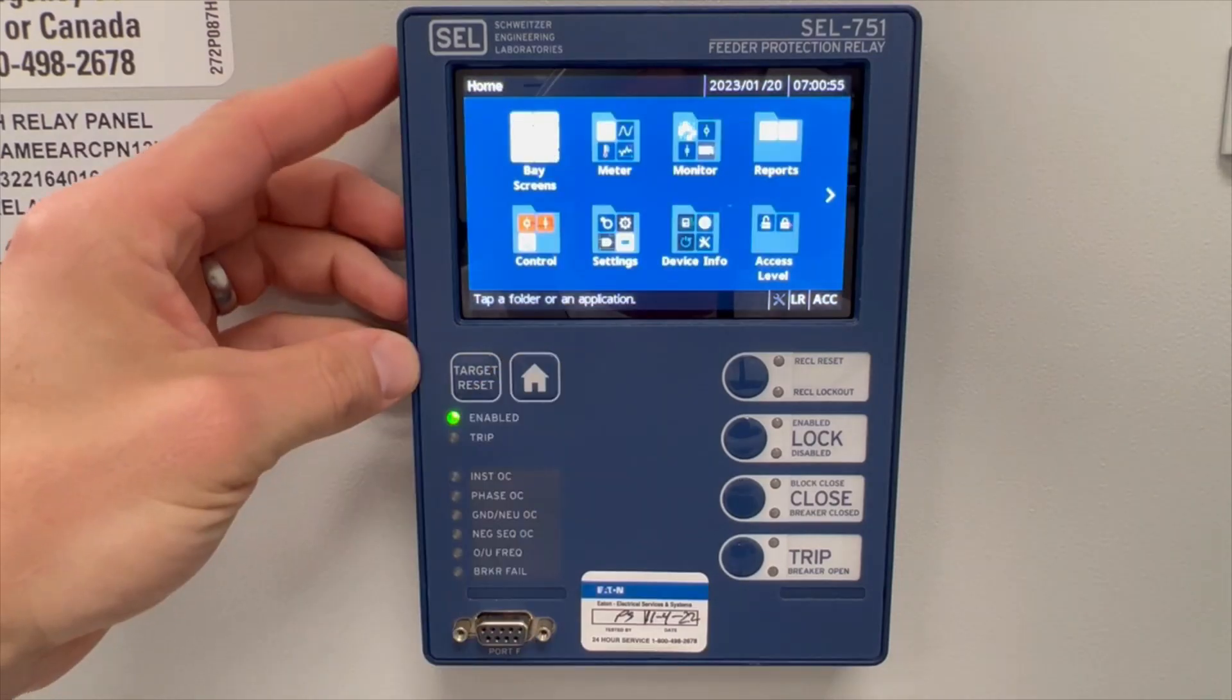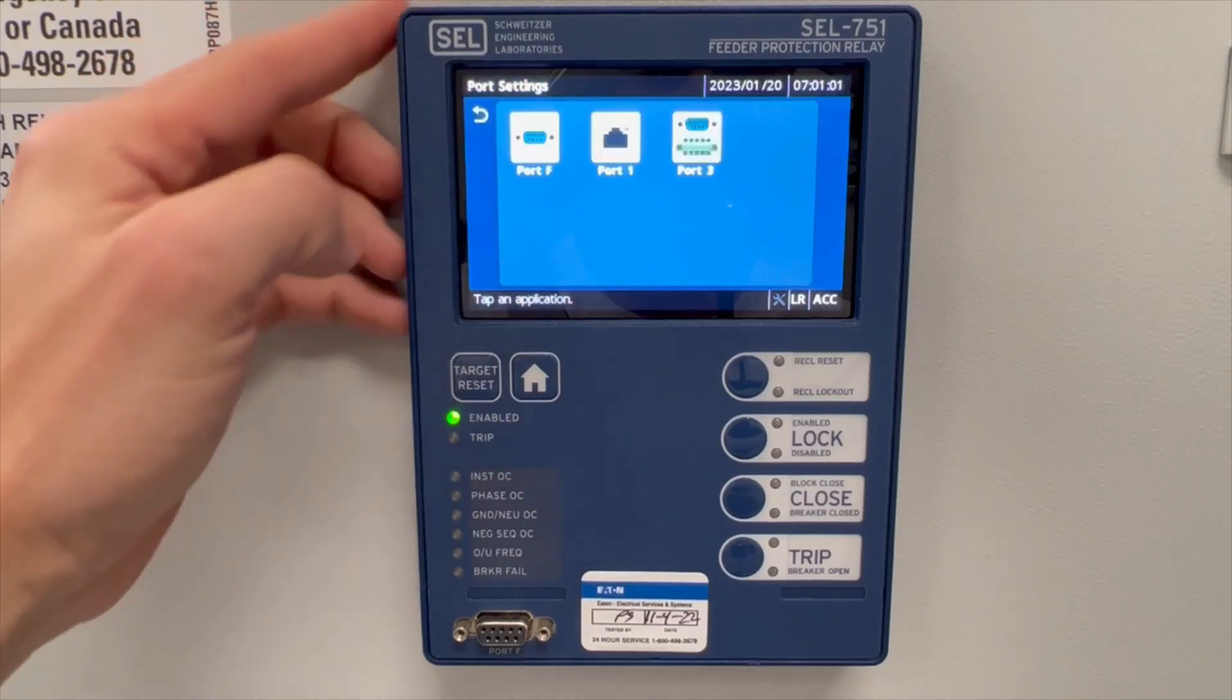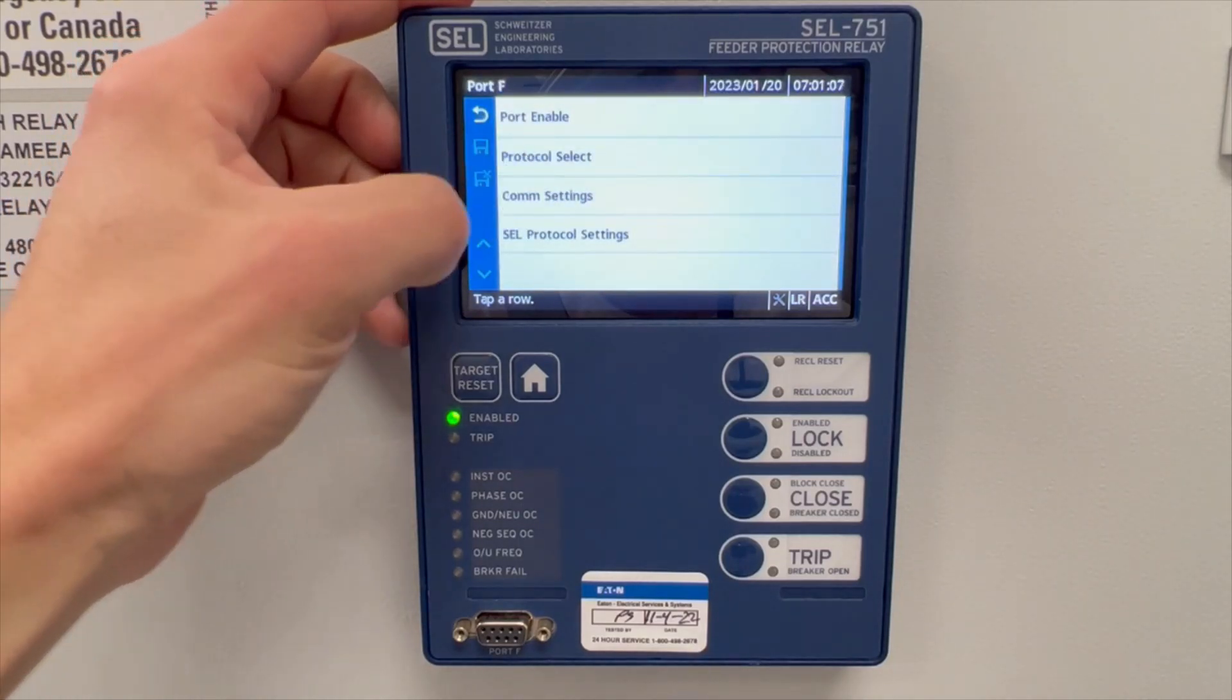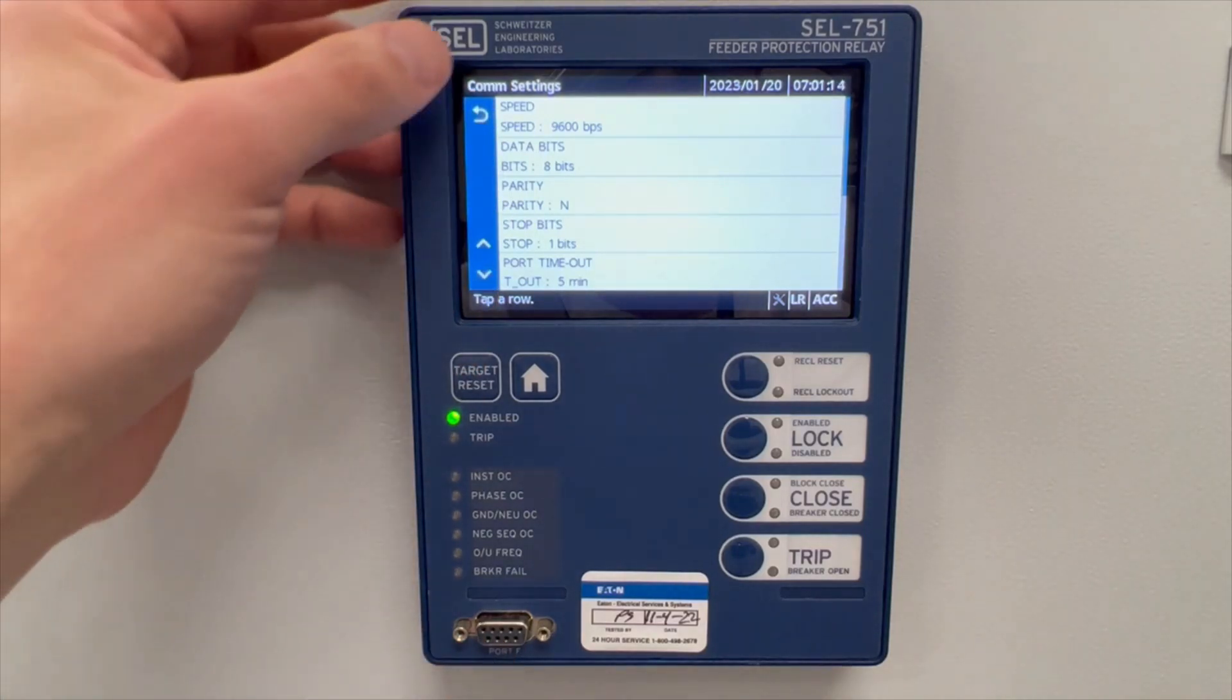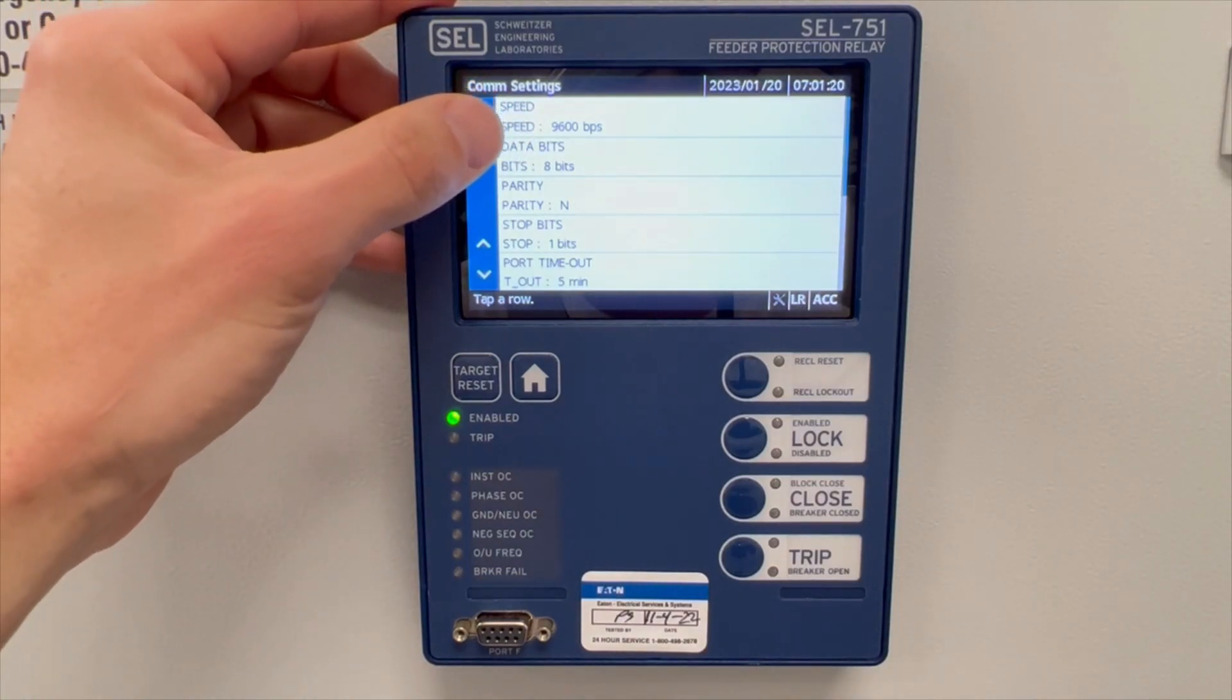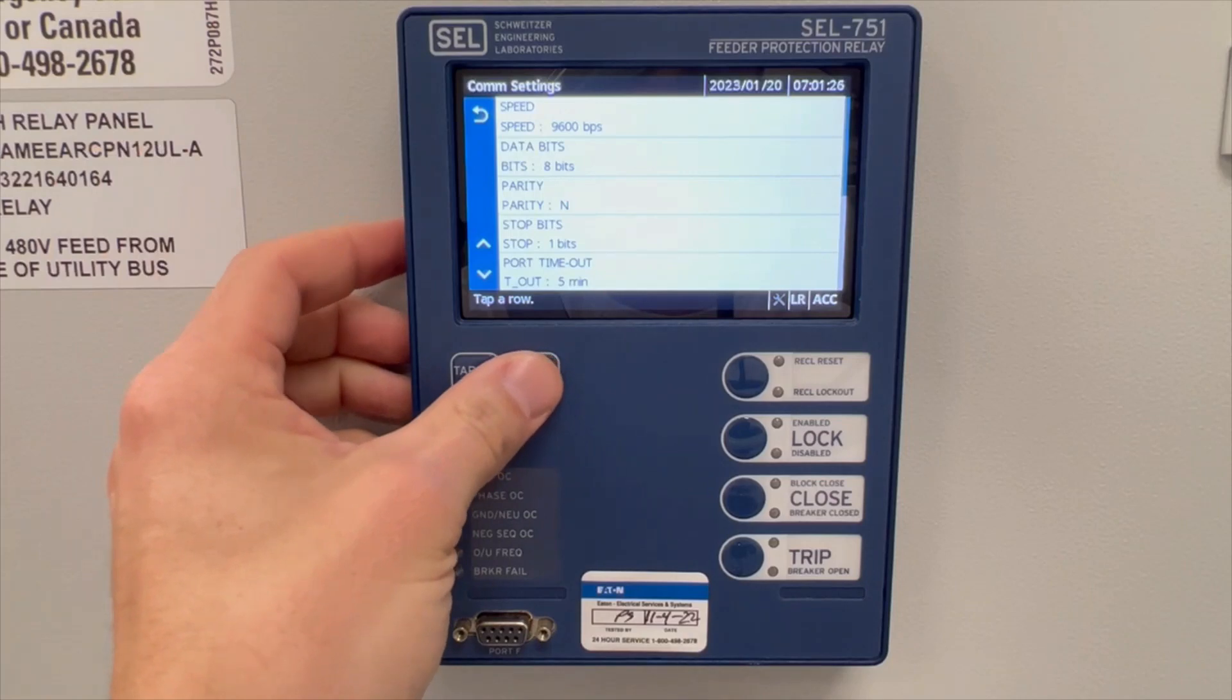To get the communications protocol, touch the settings icon. Go to port F. Port F again. Click comm settings. Here you'll see a list of settings that pertain to the port F communications. Record the speed, this is 9600. That is the baud rate that you have to put into your computer when you go to connect. Record these other parameters although a lot of these will be defaulted. Touch home.